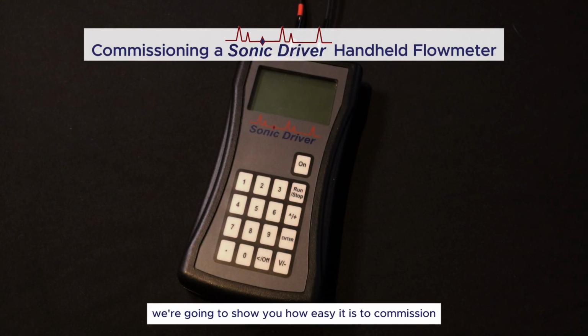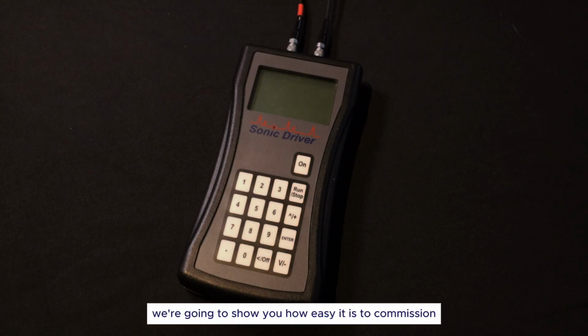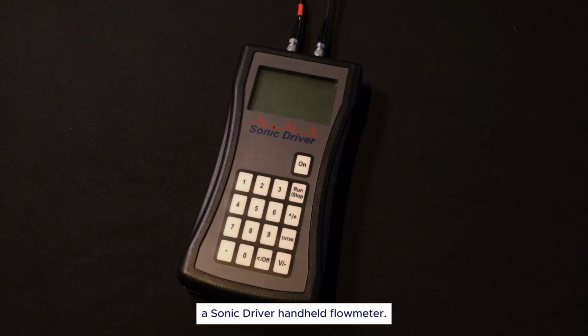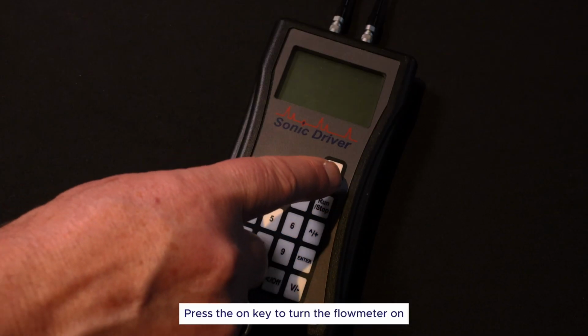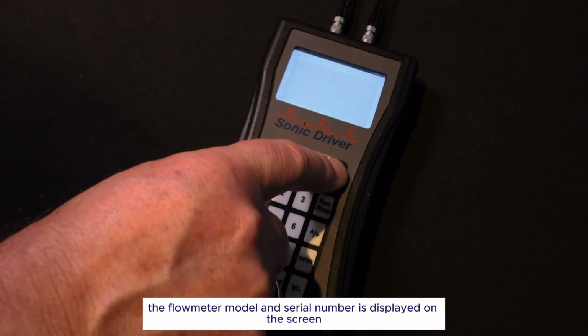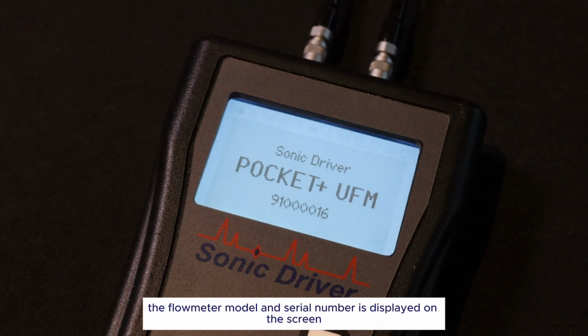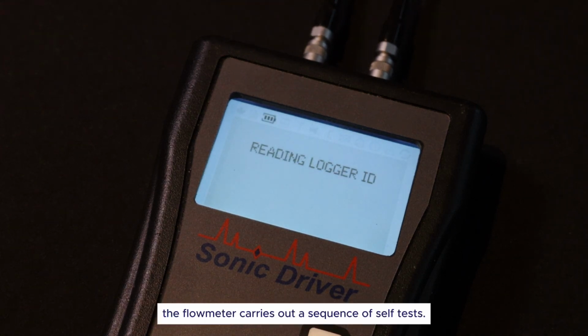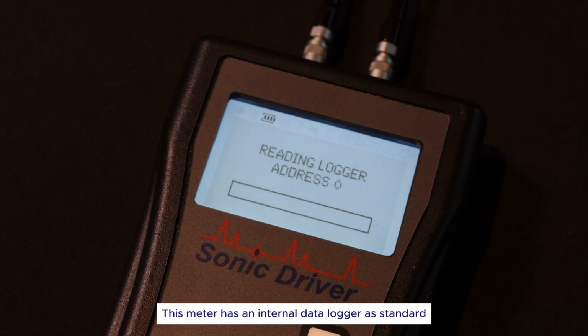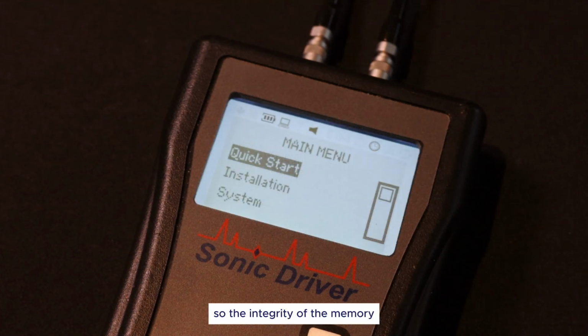Today we're going to show you how easy it is to commission a Sonic Driver handheld flow meter. Press the on key to turn the flow meter on. The flow meter model and serial number is displayed on the screen, and then the flow meter carries out a sequence of self-tests. This meter has an internal data logger as standard, so the integrity of the memory and data stored is checked.